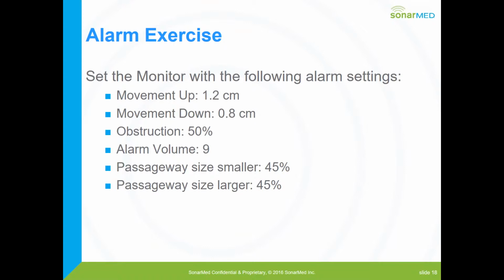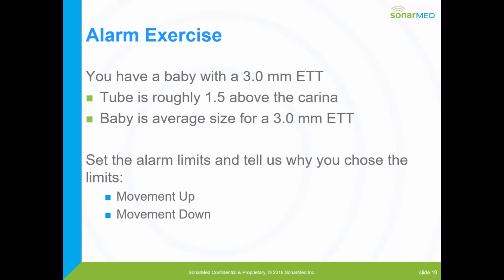And remember, once you've done that, you're going to want to confirm the changes you made. So here's another exercise. If you have a baby that has a 3.0 millimeter endotracheal tube, and the tube is roughly 1.5 above the carina, and the baby's an average size for a 3.0, how would you set the alarms, and how would you justify how you set your up and down movement alarms? So think that through as well.